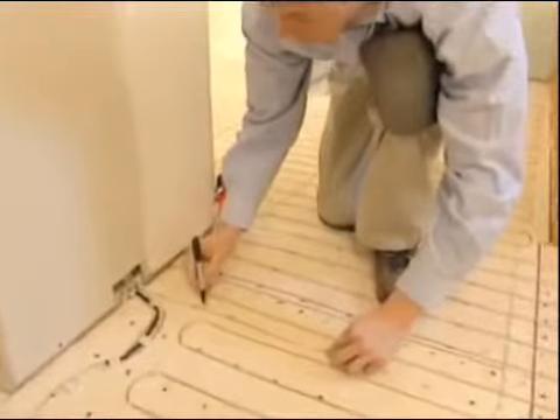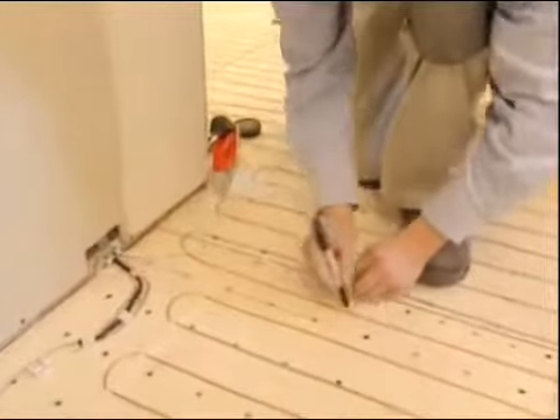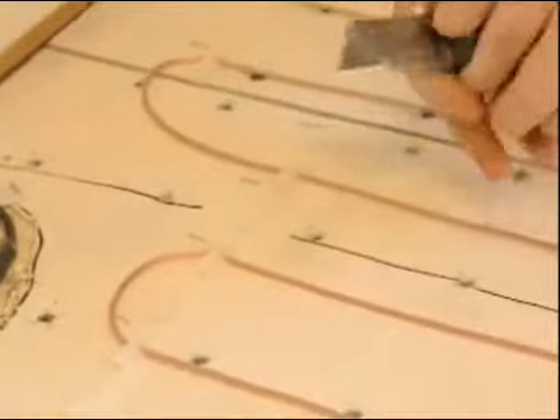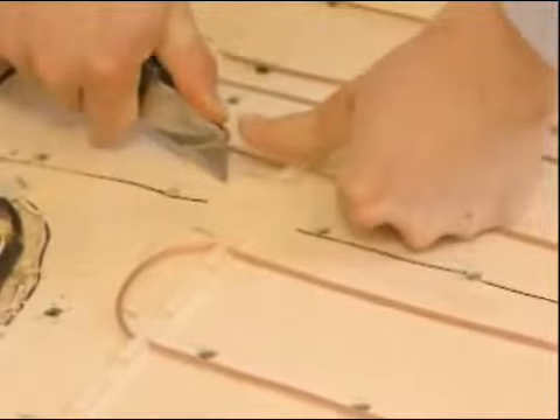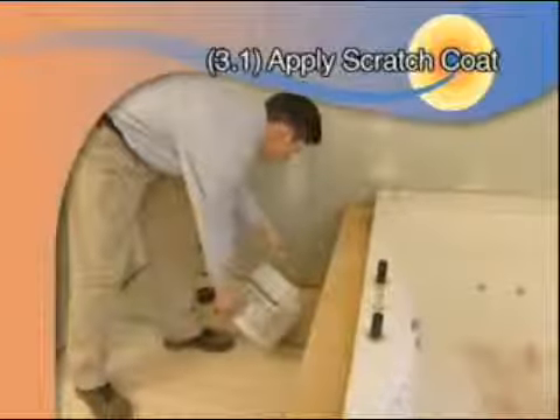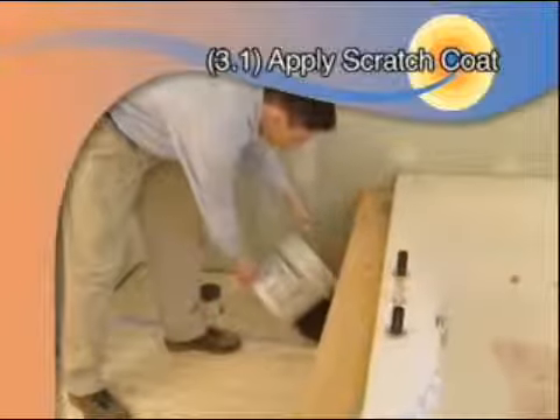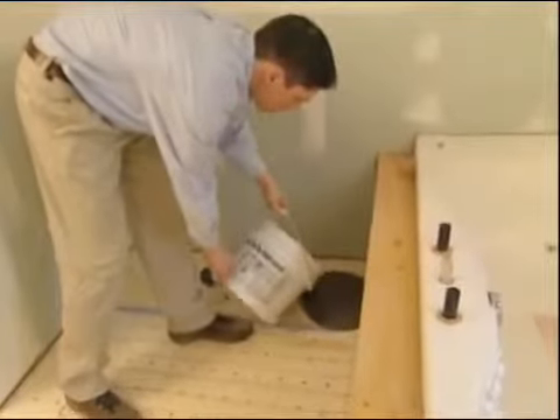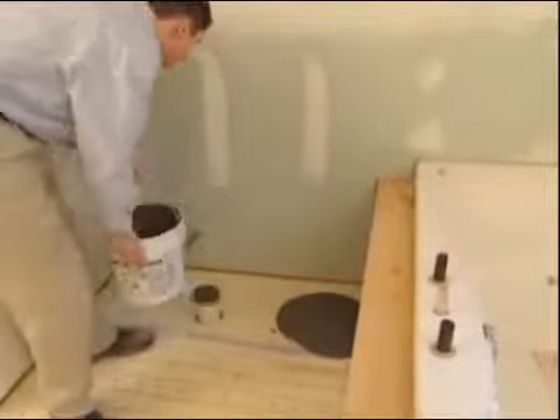Select a pair of 3-inch runs of cable on the floor to position the sensor wire. Create a channel for the sensor wire by cutting and removing the unused strapping. Fasten the sensor wire to the floor with the supplied clips, making sure you center the sensor bulb between cable runs. Using a thin-set mortar installed with the flat side of a trowel or by spreading a self-leveling compound, cover the cable with a scratch coat layer.